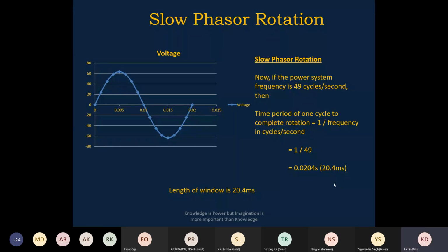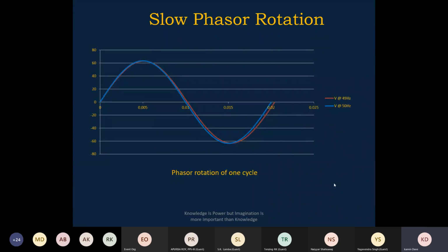So if you look at another 4 cycles, the first cycle window, and compare with the 20 millisecond window. The blue color shows the window of 20 milliseconds, and the brown color shows 49 hertz, which means a 20.4 millisecond window. So you see the error is reproduced. Sometimes, if there is a fault, the fault frequency is slightly changed.